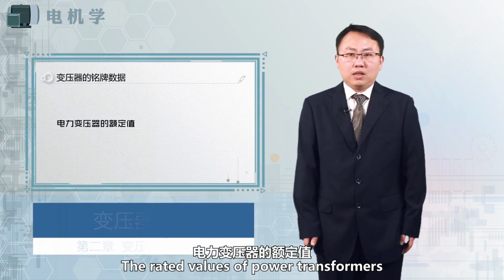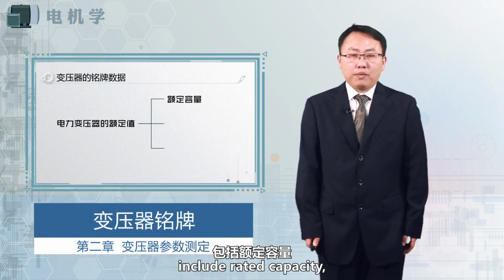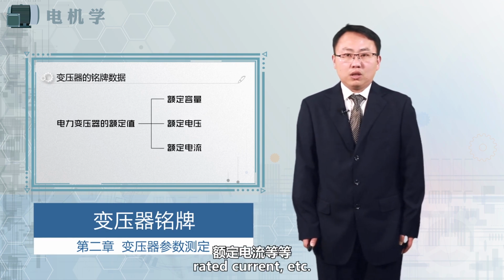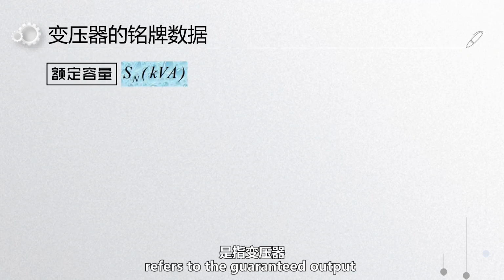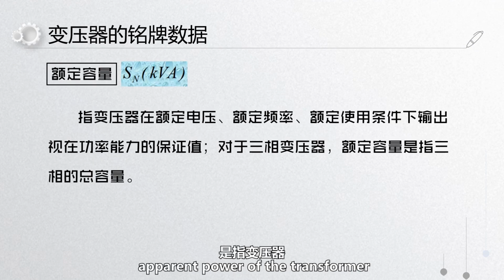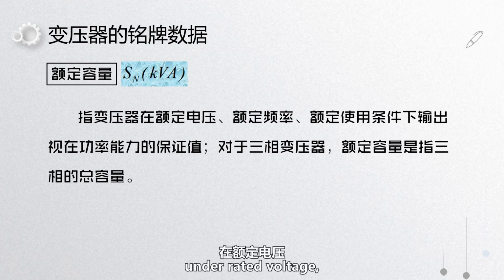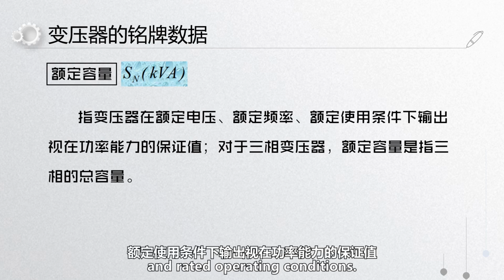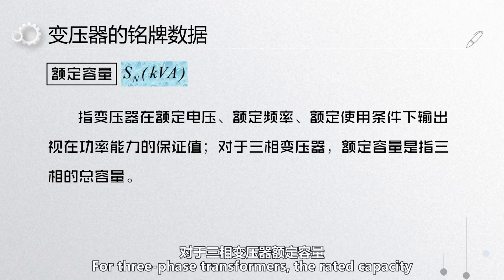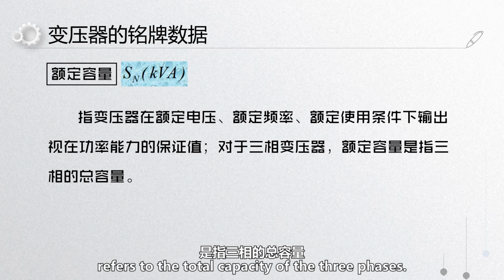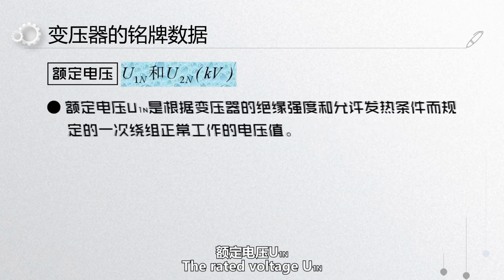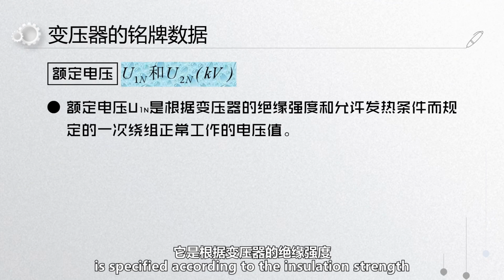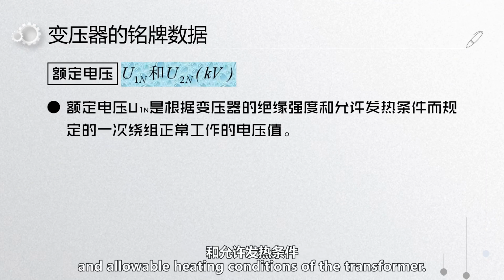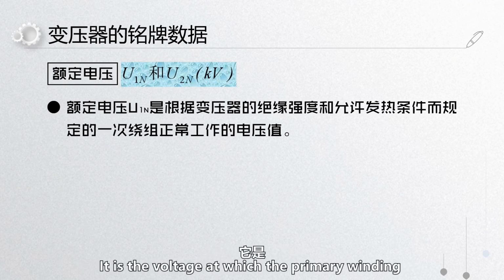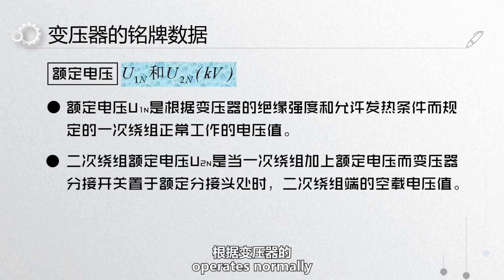The rated values of power transformers include rated capacity, rated voltage, rated current, etc. Rated capacity refers to the guaranteed output apparent power of the transformer under rated voltage, rated frequency, and rated operating conditions. For three-phase transformers, the rated capacity refers to the total capacity of the three phases. The rated voltage U1N is specified according to the insulation strength and allowable heating conditions of the transformer. It is the voltage at which the primary winding operates normally.